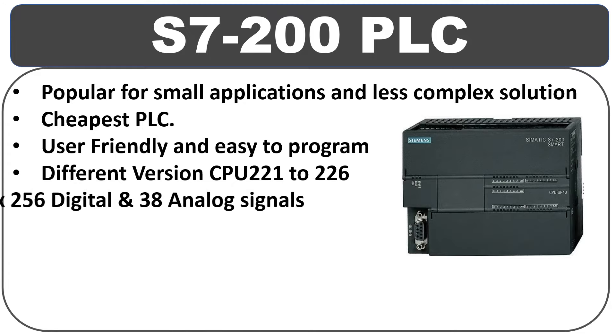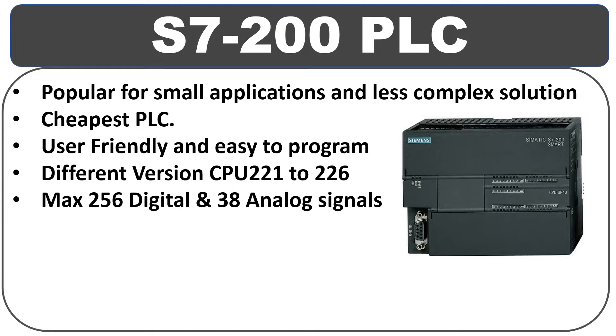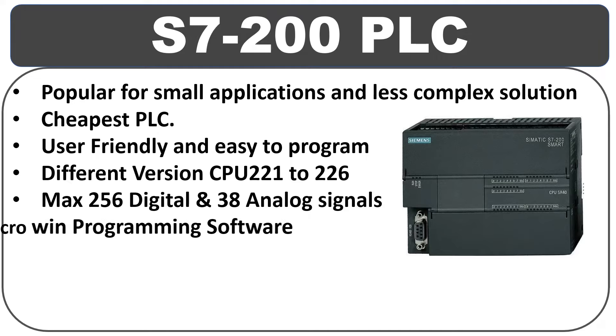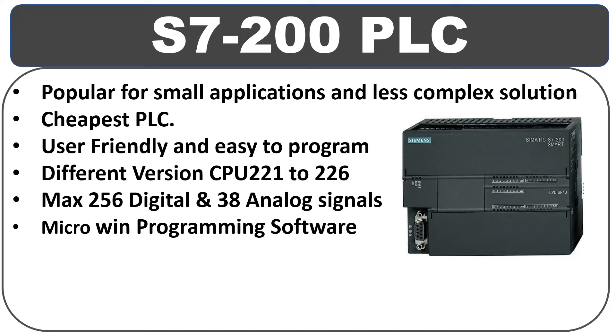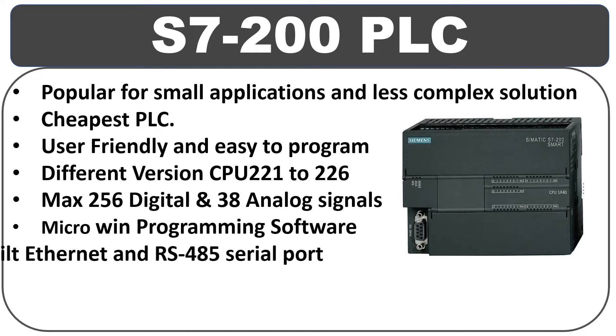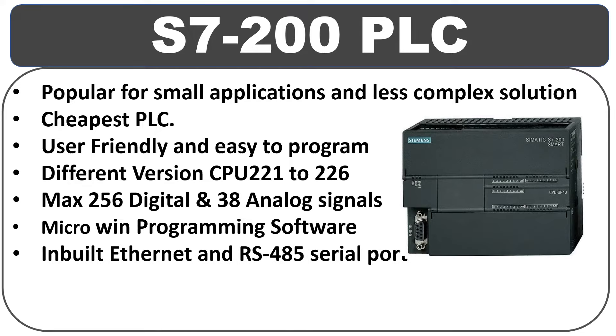The different CPU versions of the S7-200 PLC range from CPU-221 to CPU-226. The maximum I/O capacity is 256 for digital signals and 38 for analog signals. The programming software used for the S7-200 PLC is Micro/WIN, which is very easy to use. This PLC comes with one inbuilt Ethernet port and one RS485 port for serial communication.